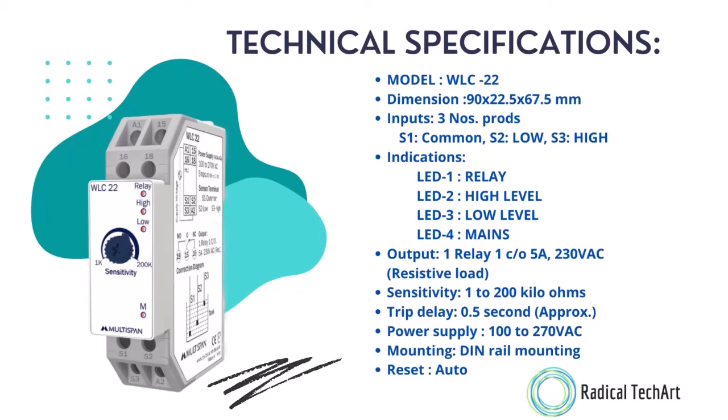Output is 1 relay 1CO, with 5 ampere and 230 volt AC ratings with resistive load. Sensitivity is 1 to 200 kilo ohms, trip delay is approximately 0.5 seconds. Power supply is 100 to 270 volt AC, mounting is DIN rail mounting, and reset is auto.